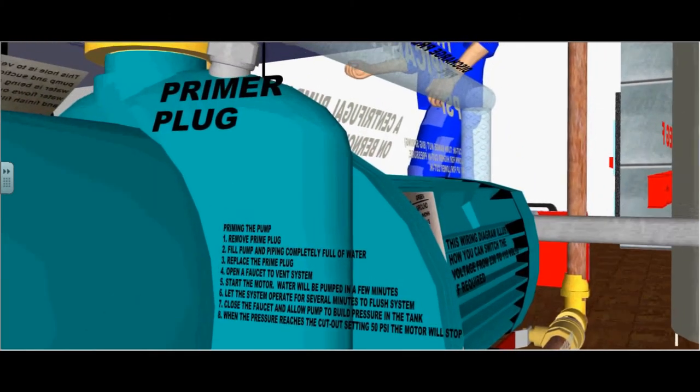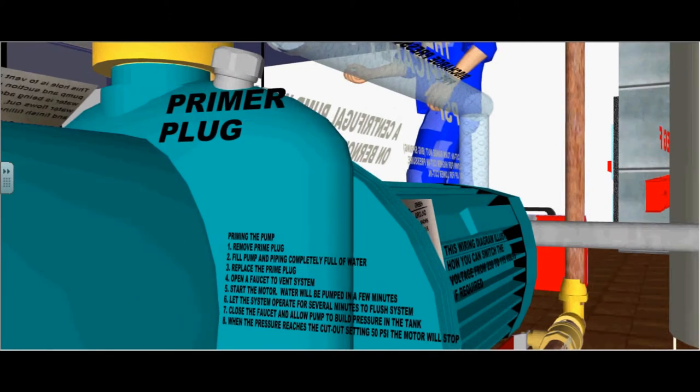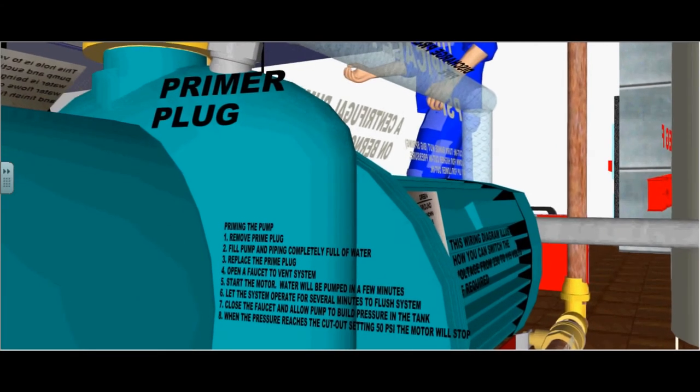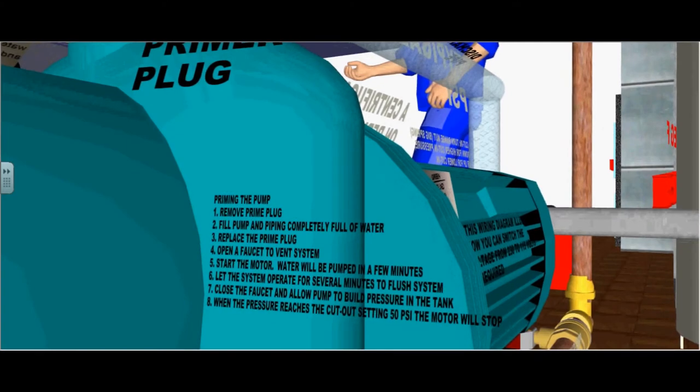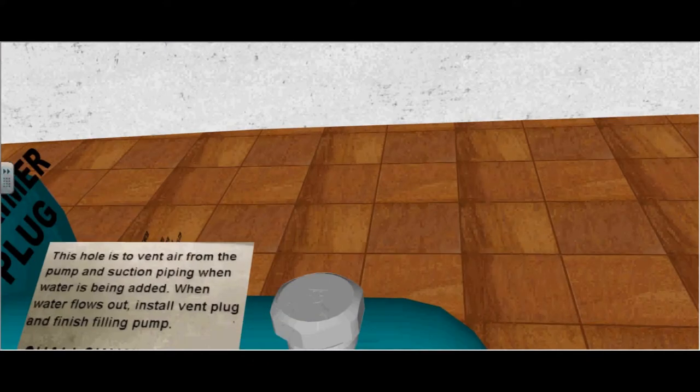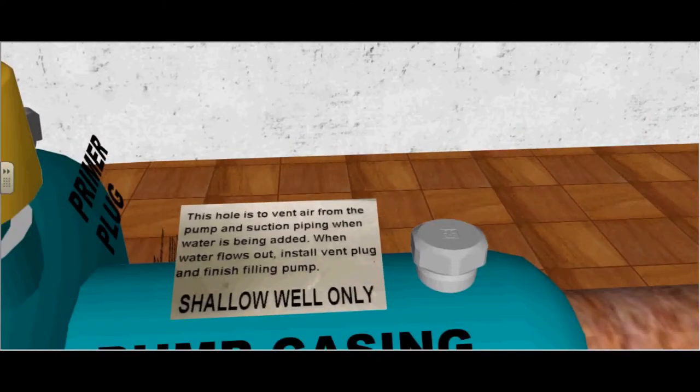Close the faucet and allow the pump to build up pressure in the tank. When the pressure reaches the cutout switch or cutout setting of 50 psi, the motor will stop. This hole is to vent air from the pump and suction piping when water is being added. When water flows out, install a vent plug and finish filling the pump.